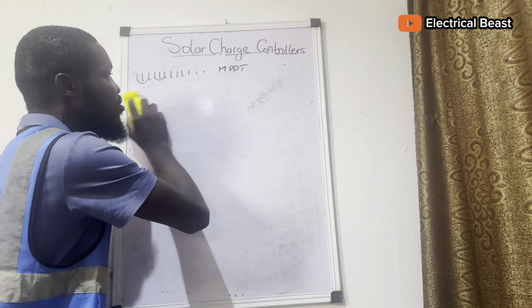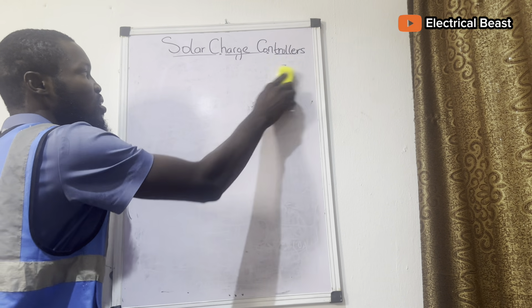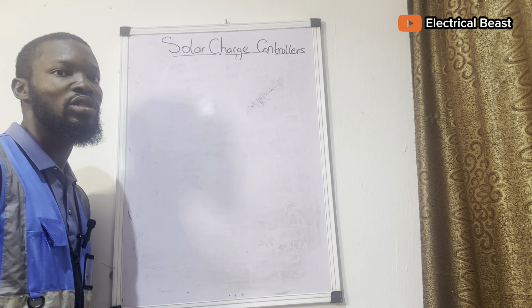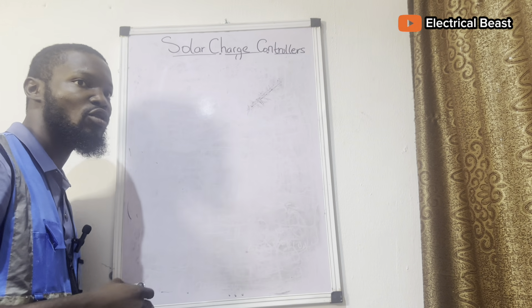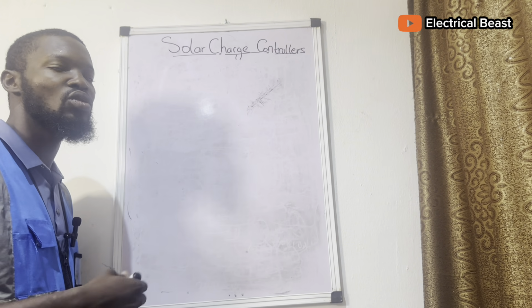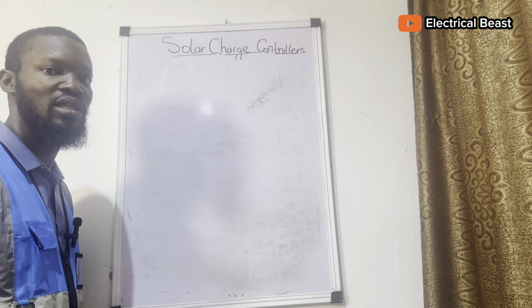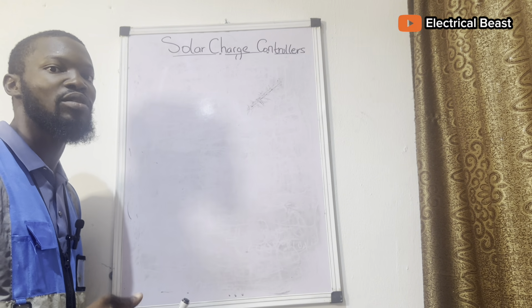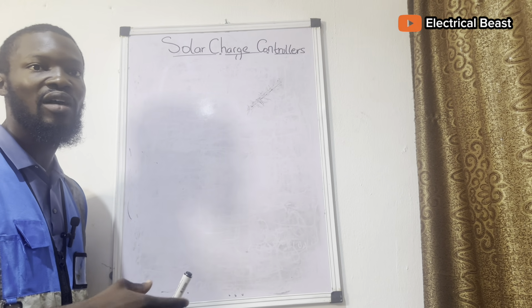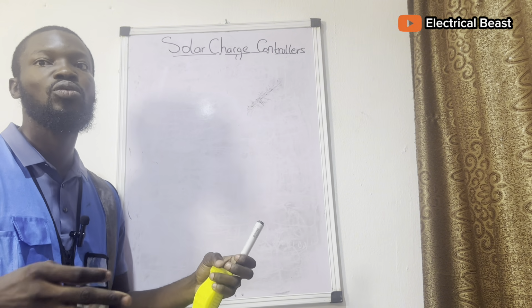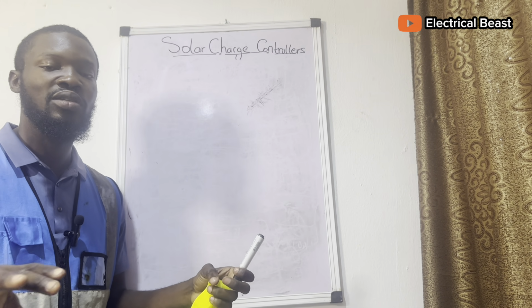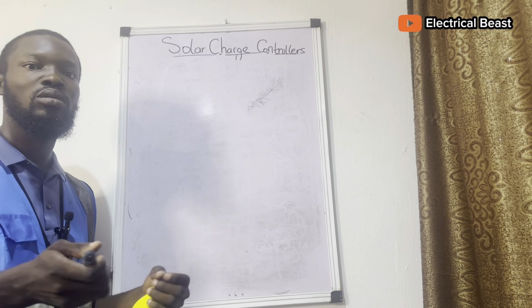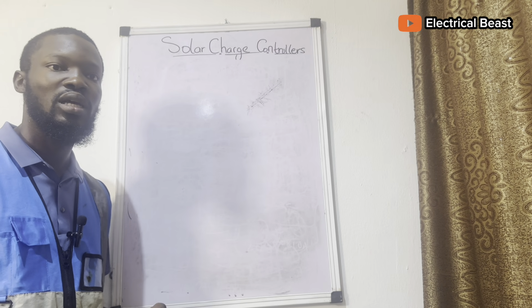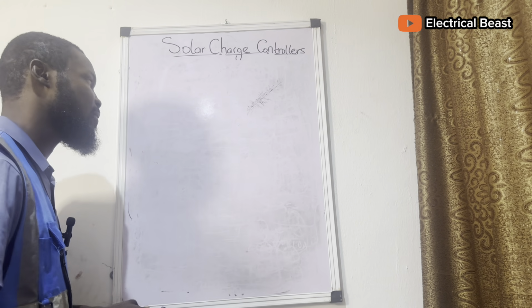MPPT gives you more flexibility, but it makes the installation more difficult because you have to connect both in series and also in parallel, and you need to use a lot of cables, even bigger size cables, because for bigger systems you'll be generating more current and also balancing voltage and current. So you'll need more cable size, and that will cost you a lot.